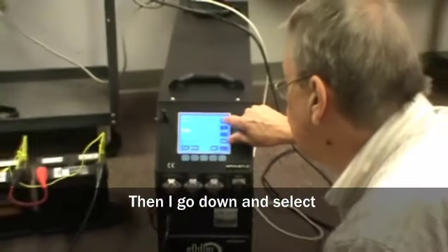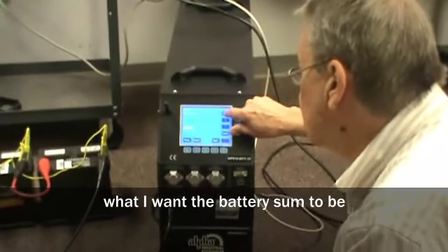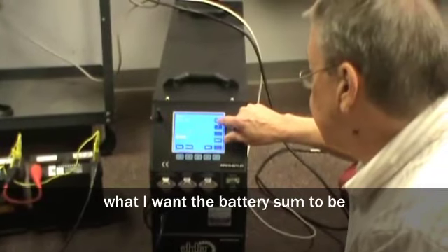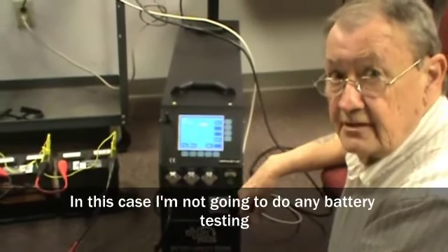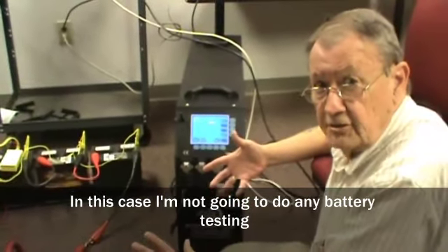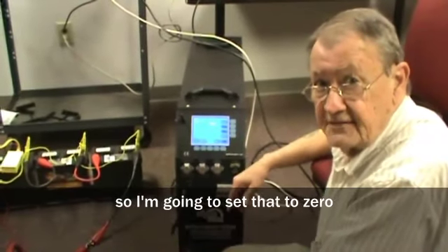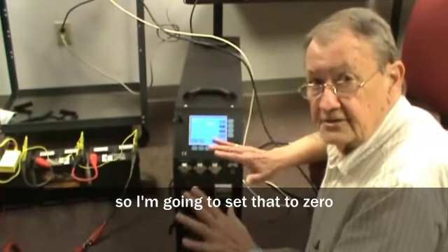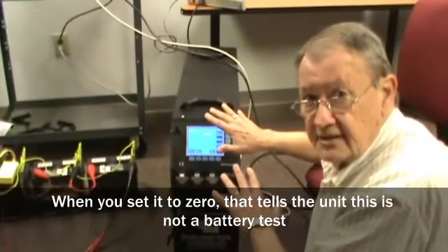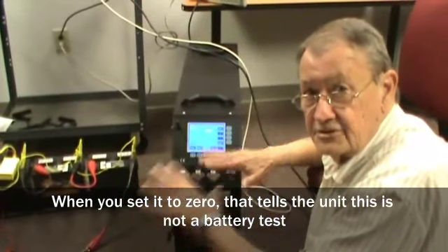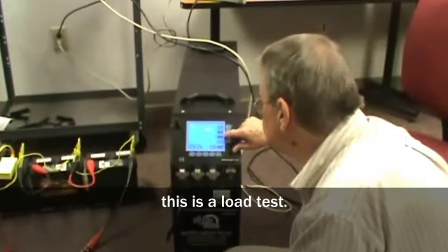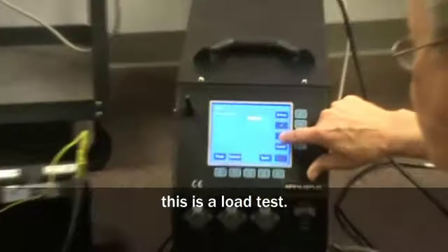Then I go down and I actually select what I want the battery sum to be. In this case, I'm not going to do any battery testing, so I'm going to set that to 0. When you set it to 0, that tells the unit this is not a battery test, this is a load test. So we select and we go back to 0.